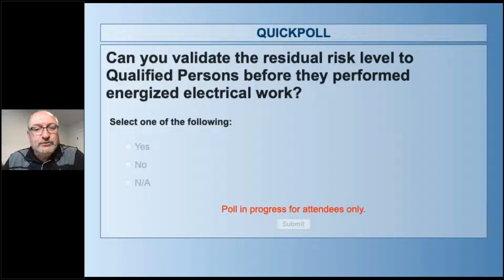Can you validate the residual risk level to qualified persons before they perform energized electrical work? This is a loaded question, because if you have an electrical safety program that's not compliant, you might not have a qualitative risk assessment requirement. Therefore, you haven't completed, as the employer, the risk assessments whose outcome identifies the hierarchy of risk control methods the worker needs to apply in the field. But how do you know they're applying the controls you expect? That's the residual risk level—the risk with controls applied. The qualified person should have these controls applied, but how do you know they've actually applied them? Can you validate that? Yes or no—prove it. Can you prove it?